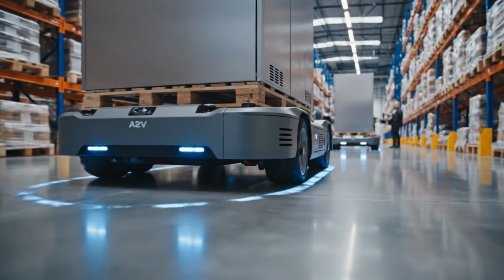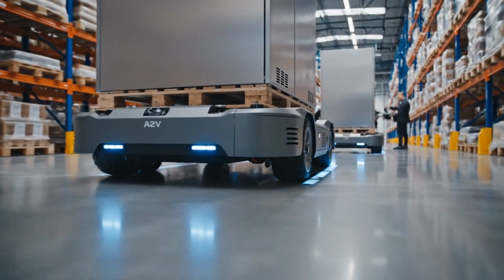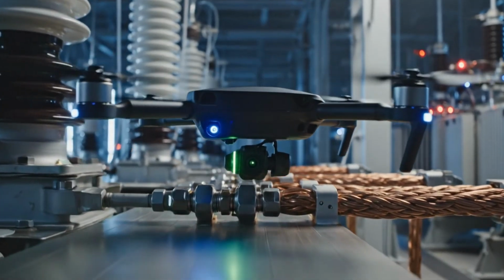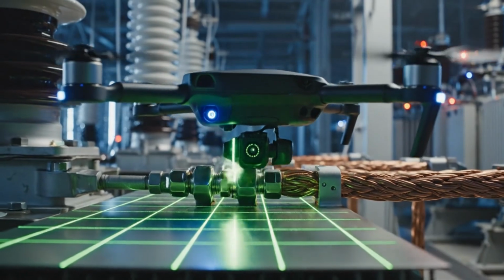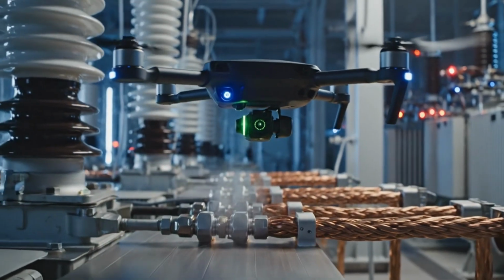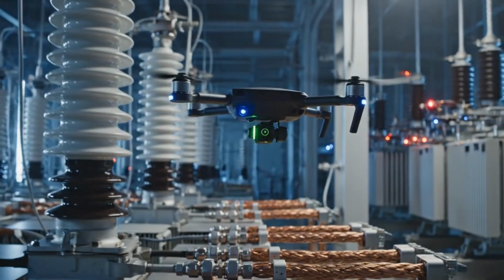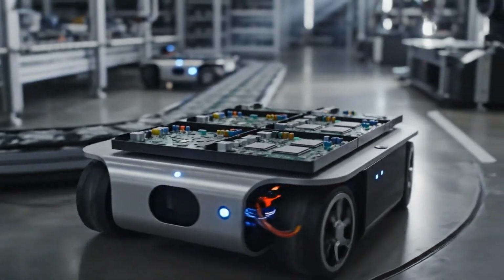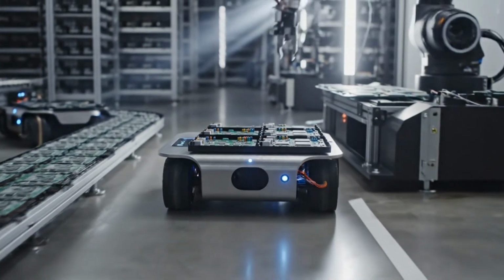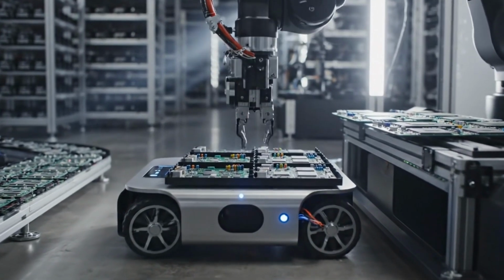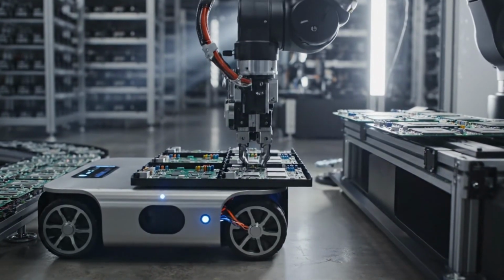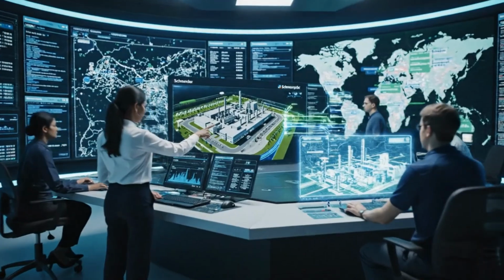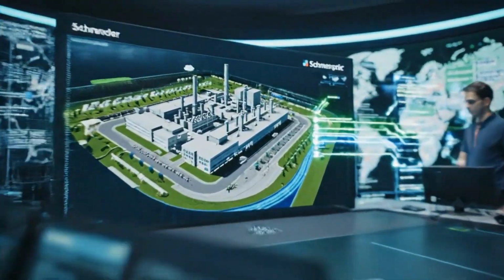Software validation runs in parallel with hardware testing. Embedded firmware, protection algorithms, and energy optimization logic are exercised under thousands of simulated scenarios. Fault injection deliberately disrupts signals, sensors, and communication paths. Systems must isolate problems, maintain safe states, and recover automatically without cascading failure.